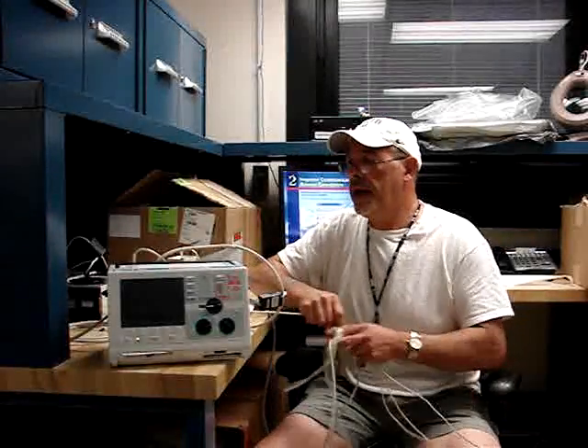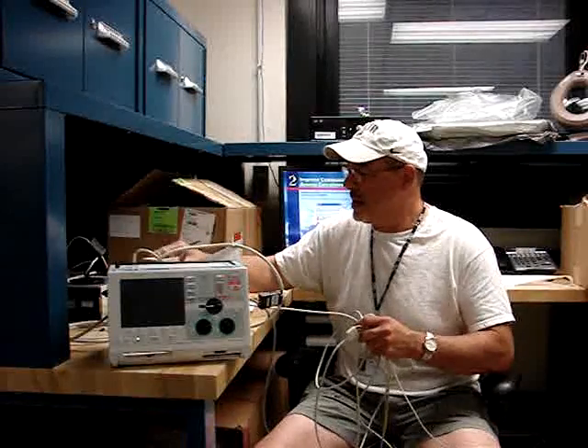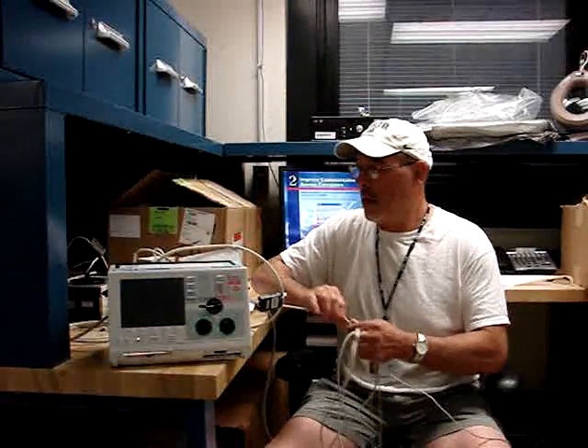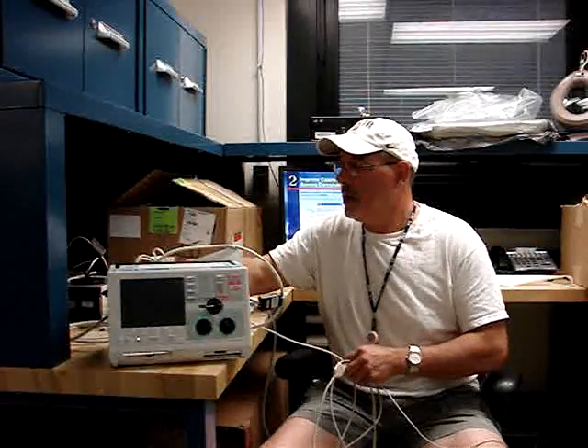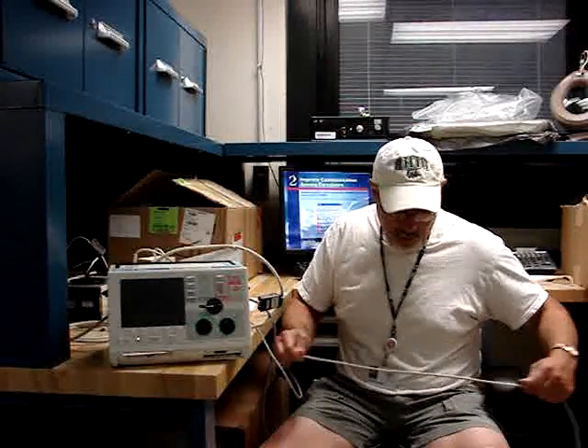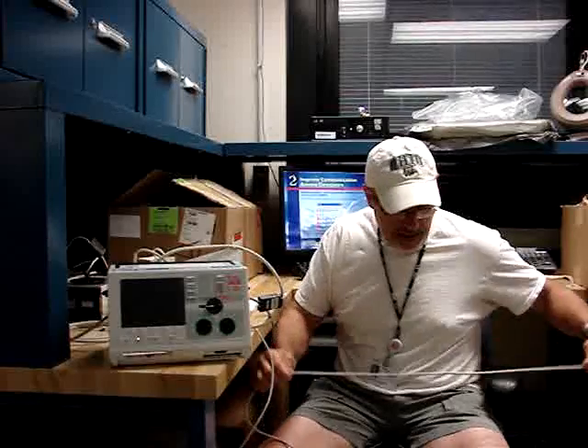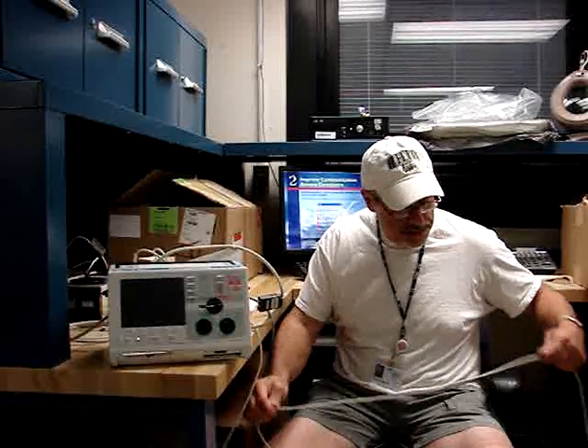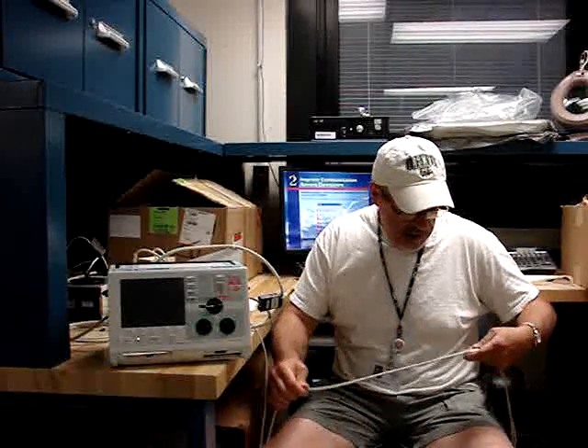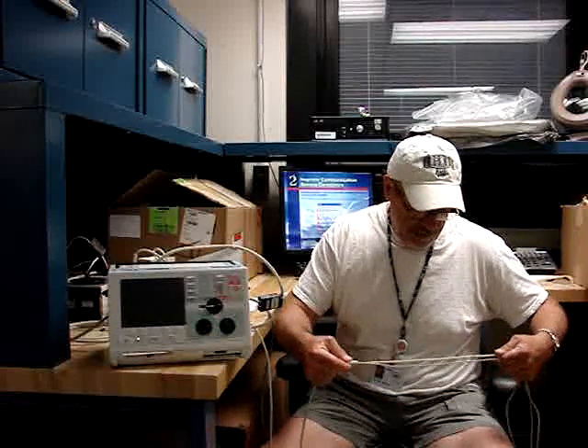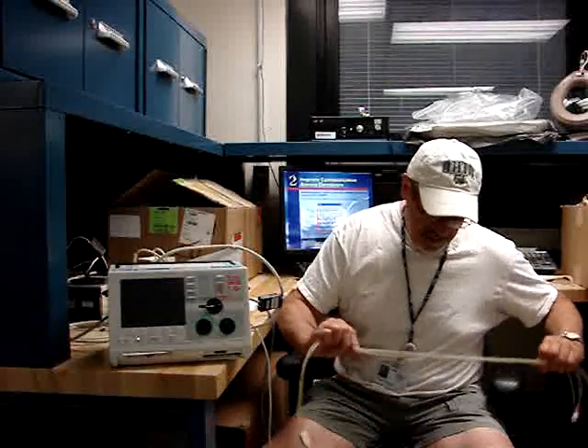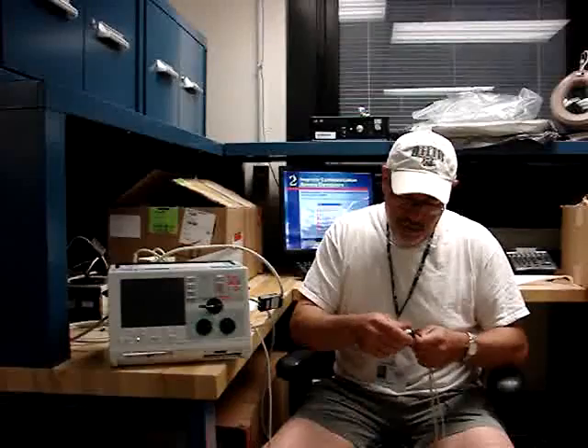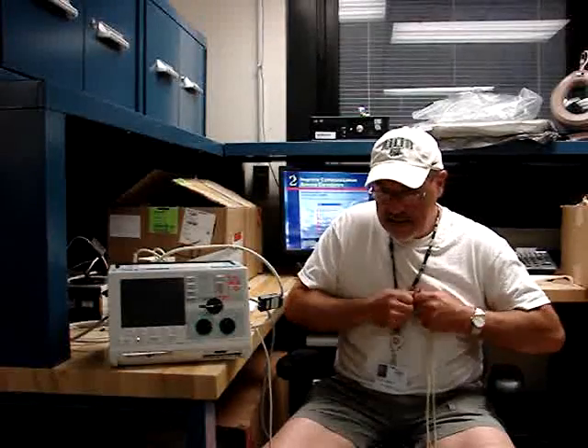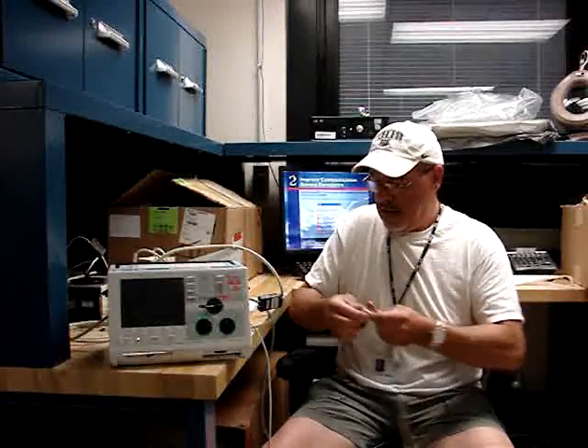Okay, on the fittings and connectors that attach to the analyzer, that's going to give us our heart rhythm. I'm going to check the cord coming out of the defibrillator for any frays, any breaks, anything that could possibly give us an erroneous reading. We look good. One thing I know we always do, we always pull on the ends to make sure they're good and tight. We are good.